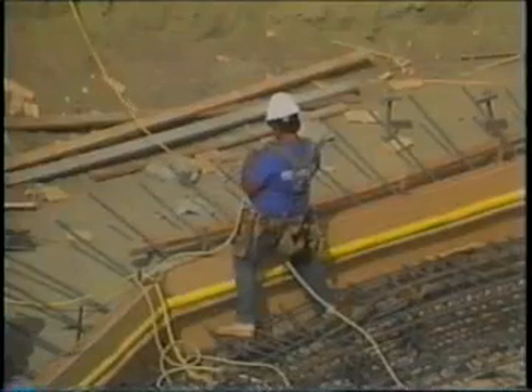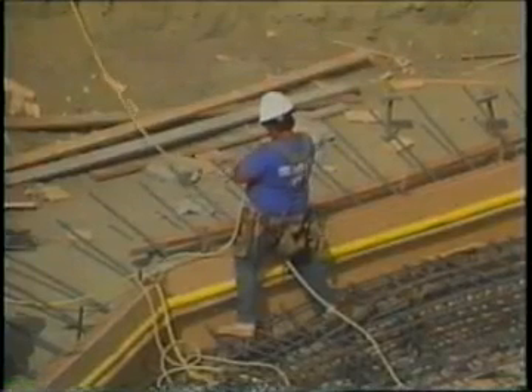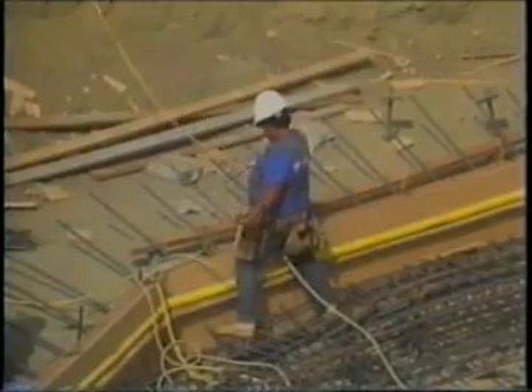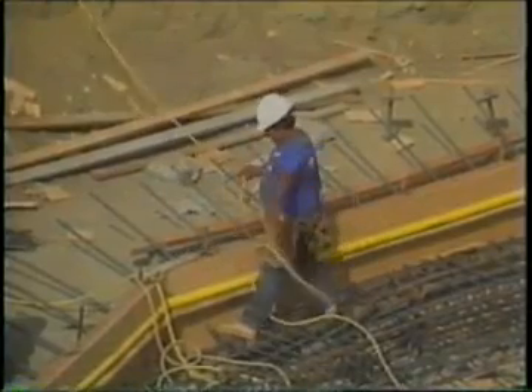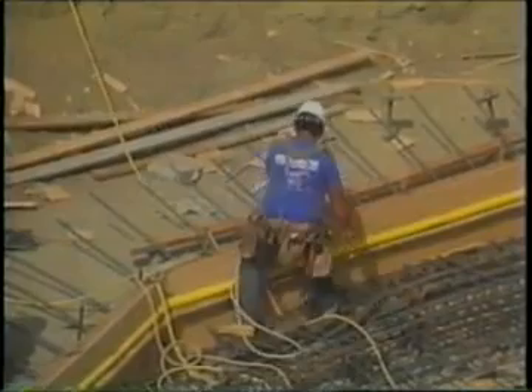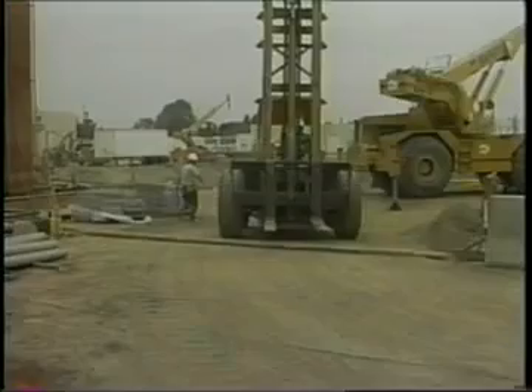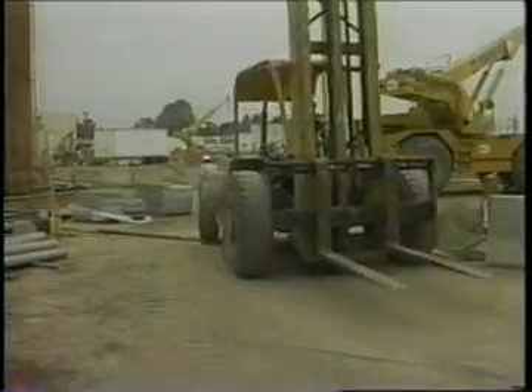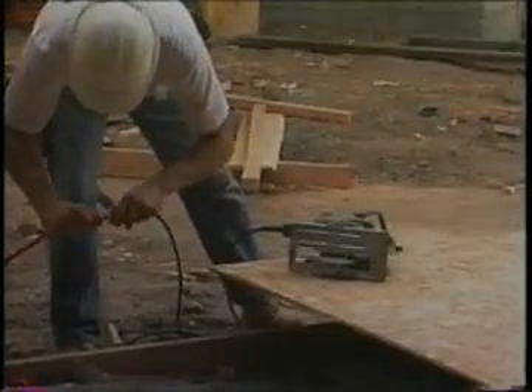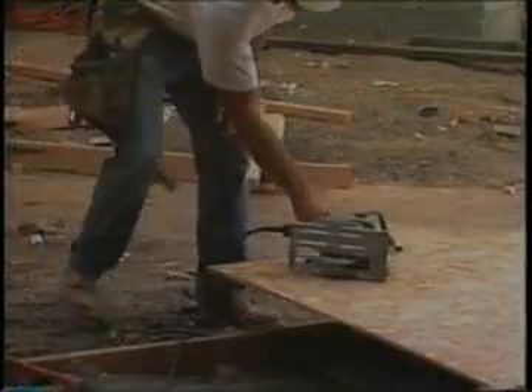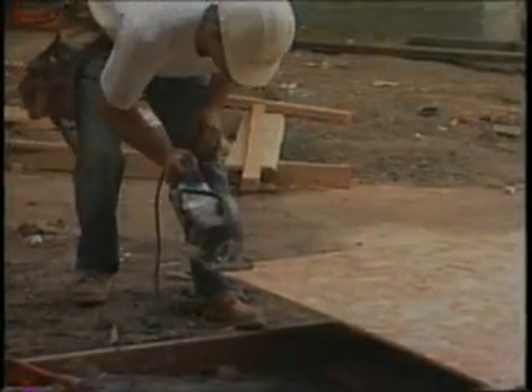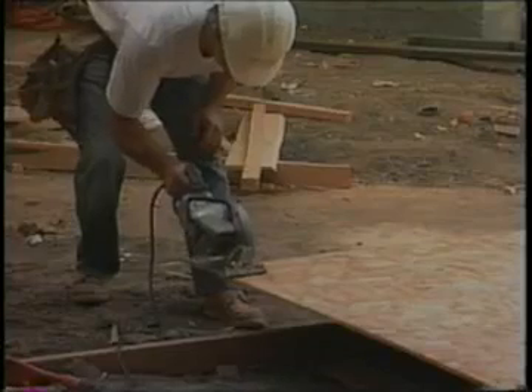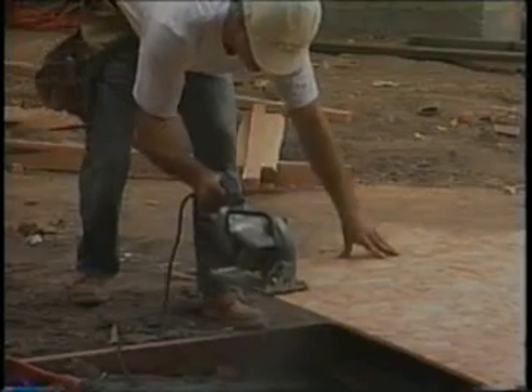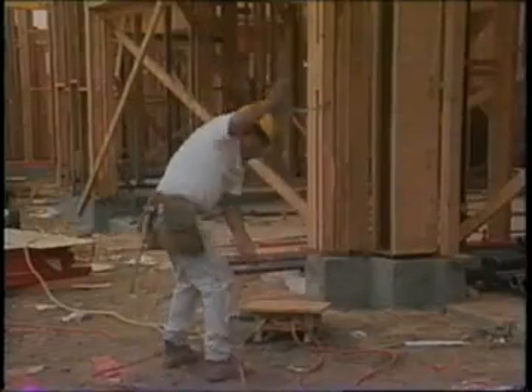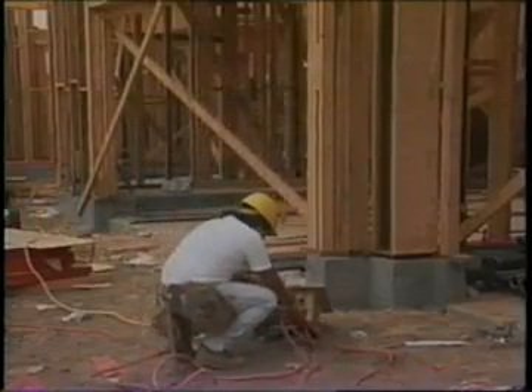With the wide use of portable tools and the use of flexible cords, connectors, receptacles, and cord and plug connected equipment, hazards are created by improper use and maintenance. Flexible cords are more vulnerable to damage than is fixed wiring. Flexible cords must be connected to devices and to fittings so as to prevent tension at joints and terminal screws. Because a cord is exposed, these terminals become more vulnerable. Improperly connected terminals is another common situation.